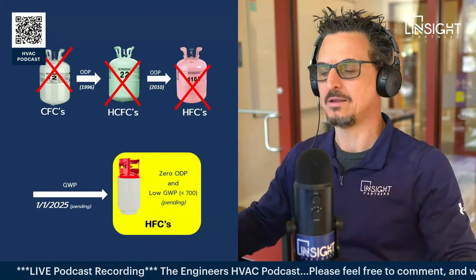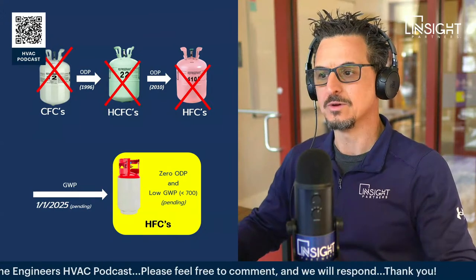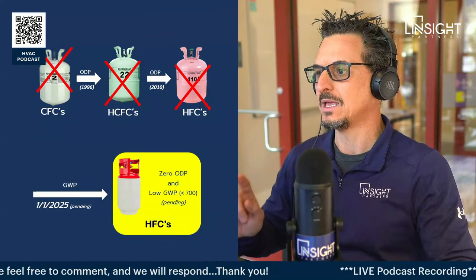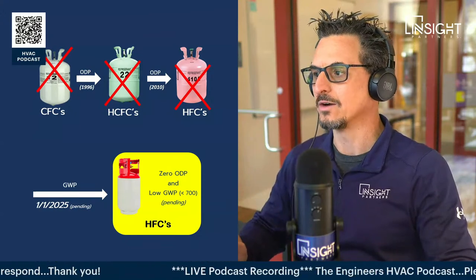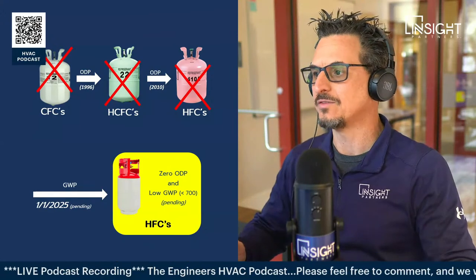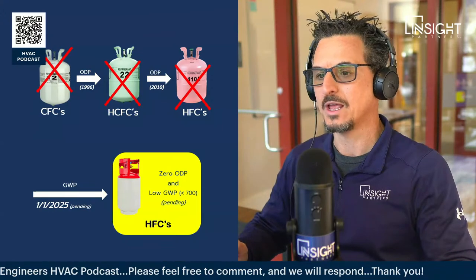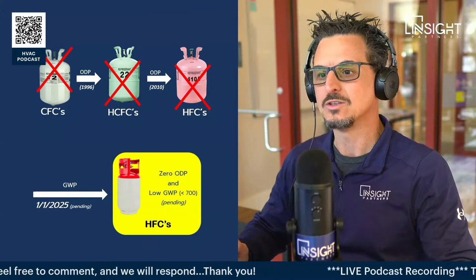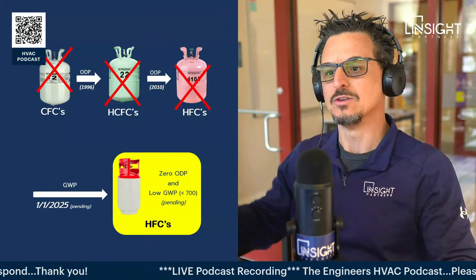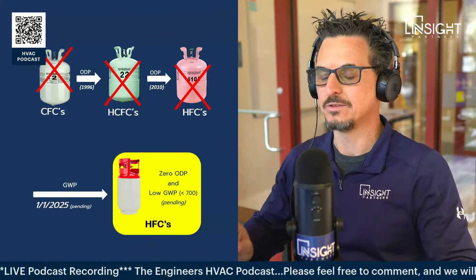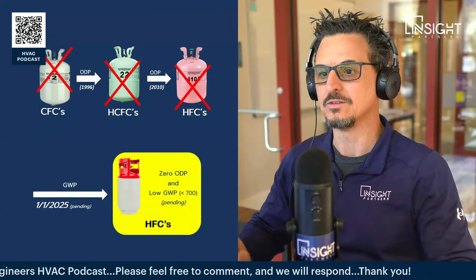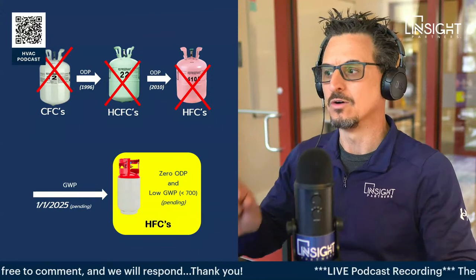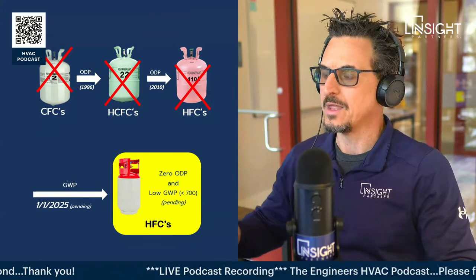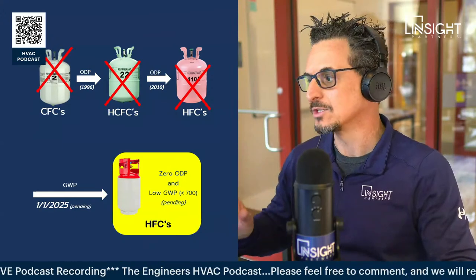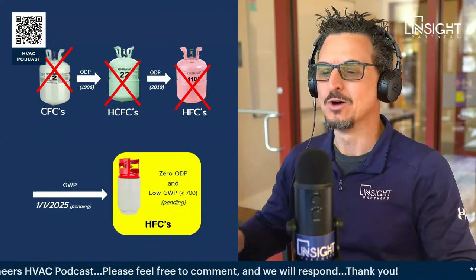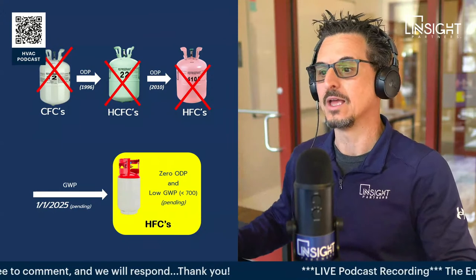I've been around since 1997, and this is my third experience with refrigerant transition. If you remember, back in '96 we were going away from R12, and then in 2010 we phased out R22 and went to R410A, which is what the majority of manufacturers use today. Now we are transitioning again. The first two transitions were basically ODP transitions - ozone depletion - trying to get rid of the chlorine in the refrigerant because that attacked the ozone layer. Now the new thing is GWP. We want lower GWP refrigerant, and that's what we're transitioning to.